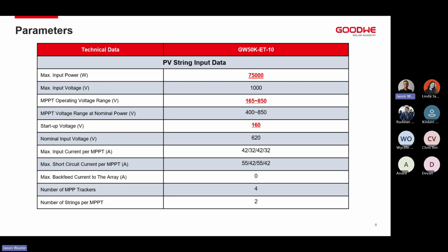From an installation standpoint, we obviously want to try and get as close as we can to the nominal input voltage, so 620 volts. At 620 volts is where we get our maximum MPPT efficiency. However, we do run at a nominal power range between 400 volts and 850 volts.